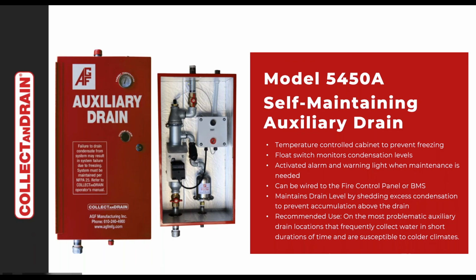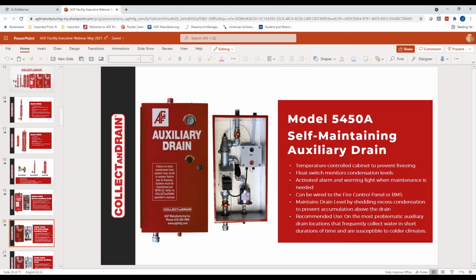And so to think about it is for every additional drip into the unit, a drip drops out of the unit. So it always maintains its air integrity above it, but when you have that very small, slow amount of condensation water dripping into these units, once it gets to that diversion, every drip in is a drip out. So in the event there was a system trip and the system was filled full of water, then the float switch would activate. It would tell you that the thing is completely full and needs to be emptied. But in its normal state, it will just drip out the water that accumulates in the system.